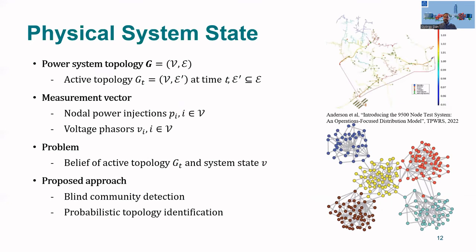To give you an idea of estimating the physical system state, consider, for example, a power distribution system that has a certain physical topology. Let's call this the graph G. Now, at any point in time, the active topology of this power distribution system is a subset, subgraph of this graph. This we call the active topology. What can we observe about this system? We can obtain a measurement vector, which consists of power injections at the nodes and voltage phasors at the nodes. And our objective is to build a belief about the active topology and the system state, that is, the voltage phasors at the nodes. What we propose is to use a combination of blind community detection and probabilistic topology identification for solving this problem.